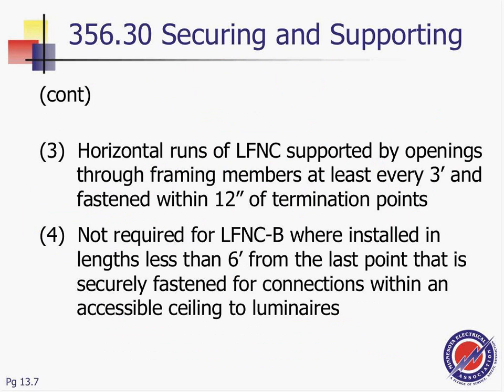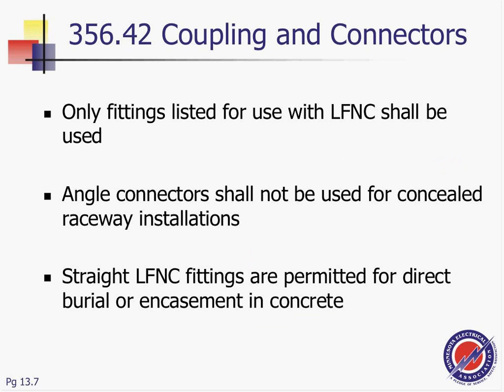Horizontal runs and runs through openings, the same thing, guys. Every 3 feet and within 12 inches. Securing is not required for B where installed in length less than 6 feet from the point that is securely fastened or connected to the luminaire, so you don't have to support it. Again, back to the luminaire in an accessible ceiling, that's your fixture whip. You don't need to support it if it's a fixture whip. Alright, guys, basically every 3 feet and every 12 inches, fixture whip 6 feet, 3 feet flexibility, and only for B. Basically, that's B. C and A are not to be used for less than 6 feet. So it's only B.